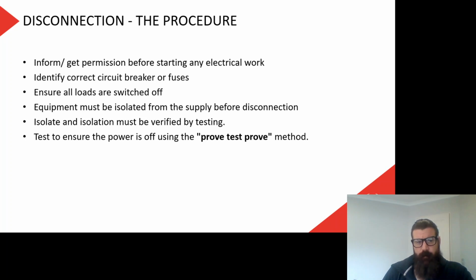Okay, so our disconnection procedure, we inform the person, we get permission. We identify the correct circuit breaker, as we said before, and there's various methods to do that, but somehow we must identify the correct one. We ensure that all the loads are switched off, so anything that's on that circuit, particularly again if it's computer equipment or something, we shut that down before we switch the power supply off. Equipment must be isolated from the supply before disconnection, so we're going to switch it off before we touch anything.